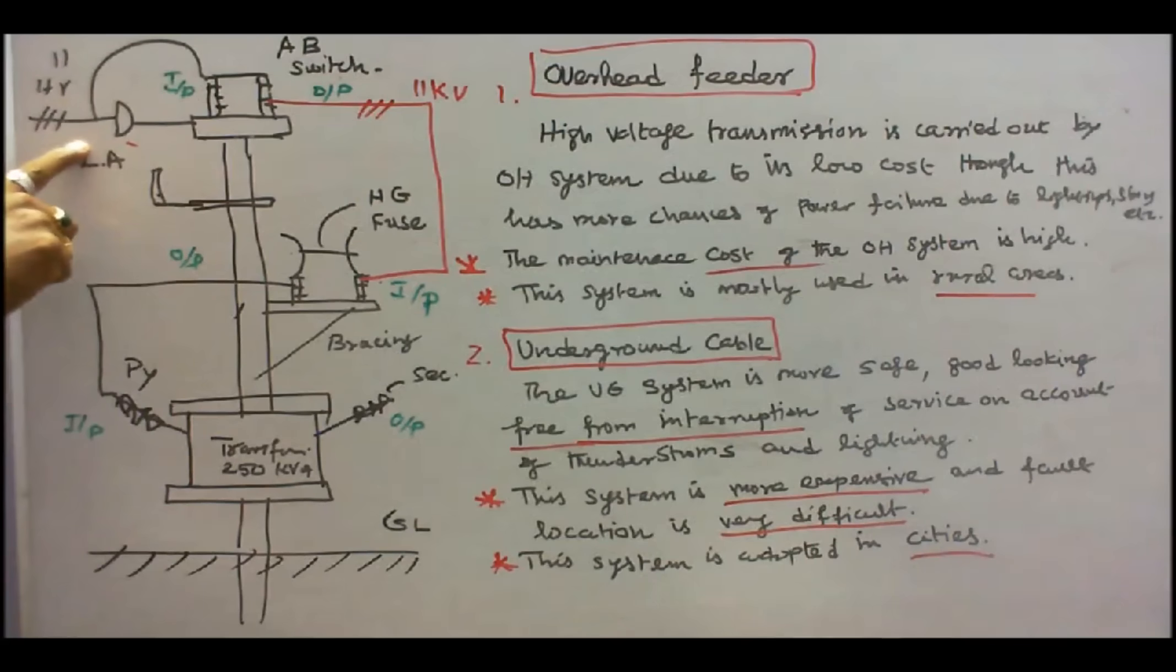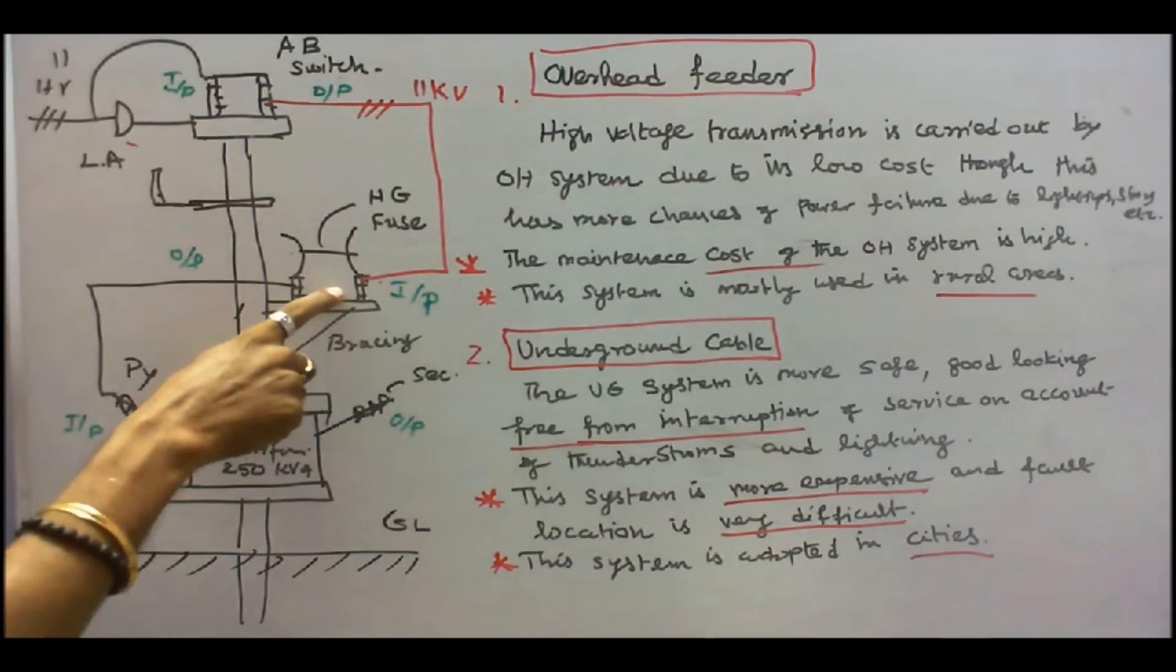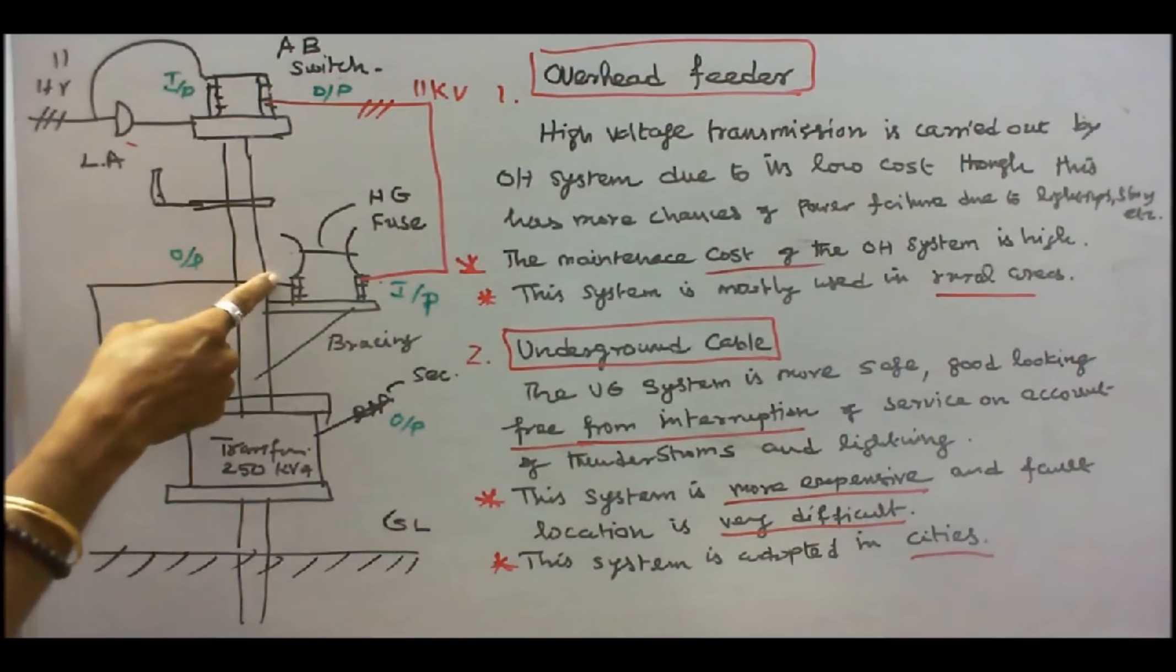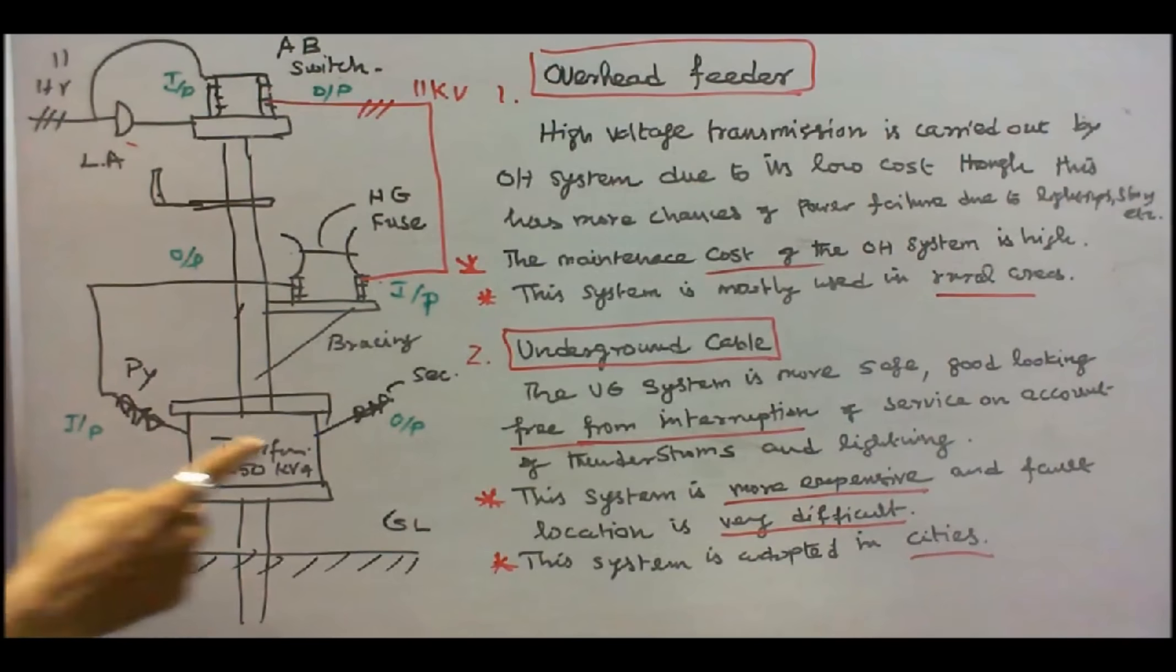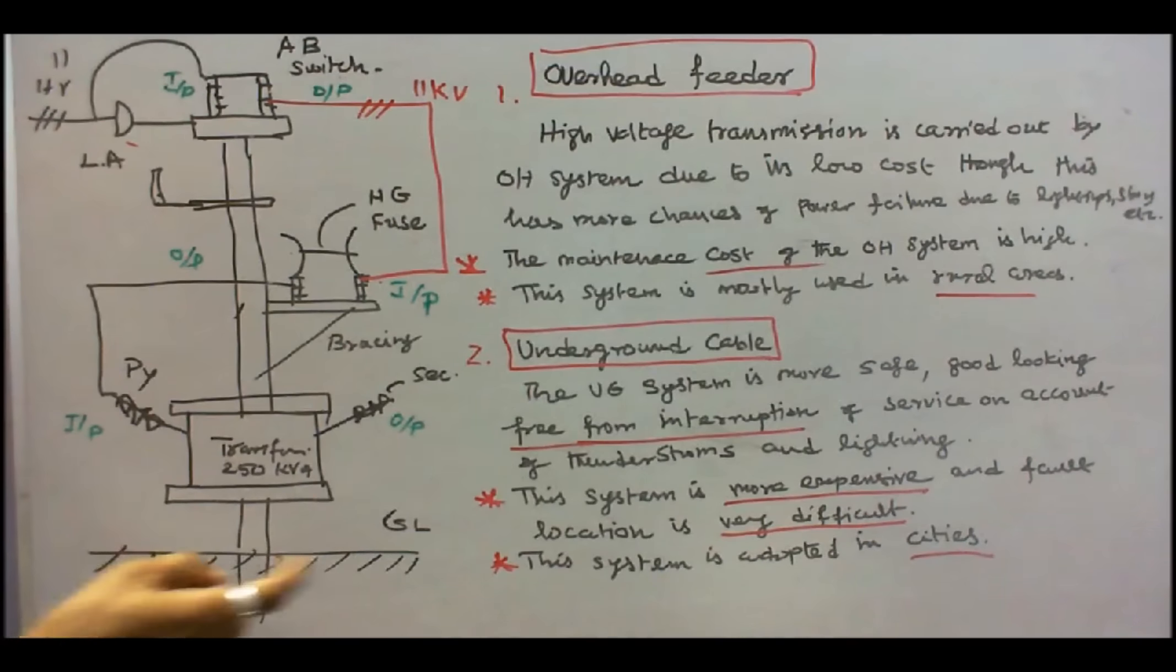Here, the 11KV line is incoming. This is the disk insulator. This is set to the input of the air brake switch. The output of the air brake switch is put into the horn gap fuse unit input. The output of the horn gap HG fuse unit comes to the primary winding of the transformer. The secondary winding goes to the control board. Now, we will see the control board.